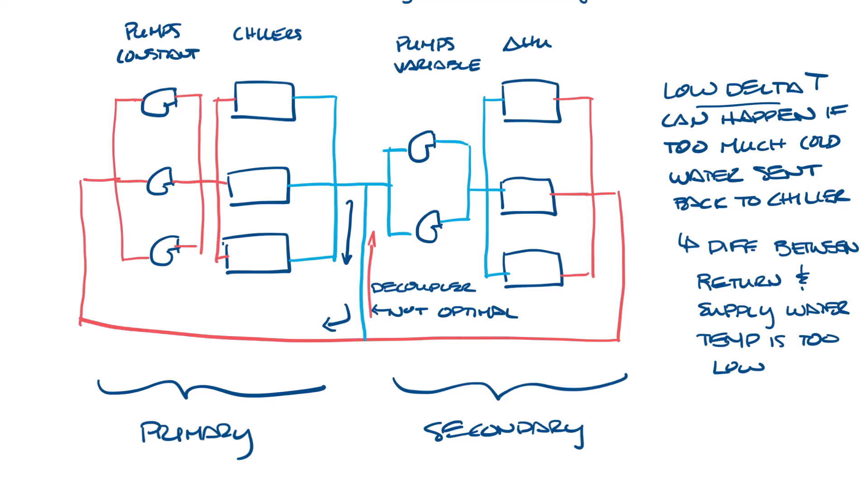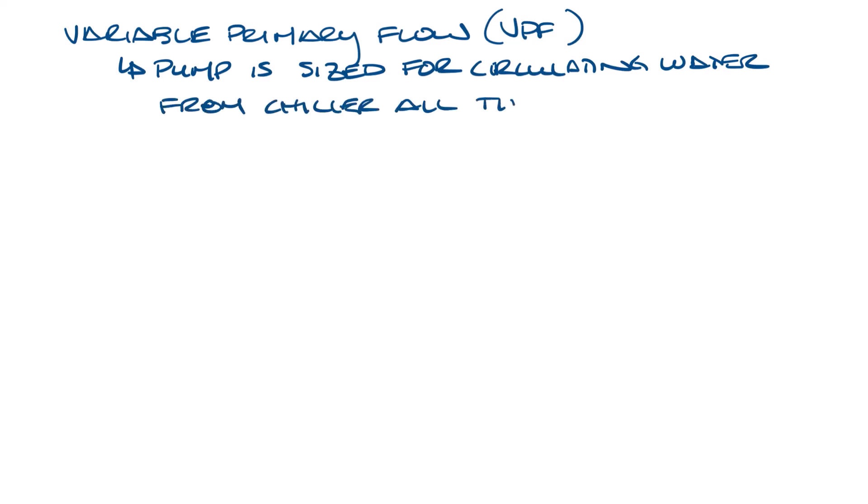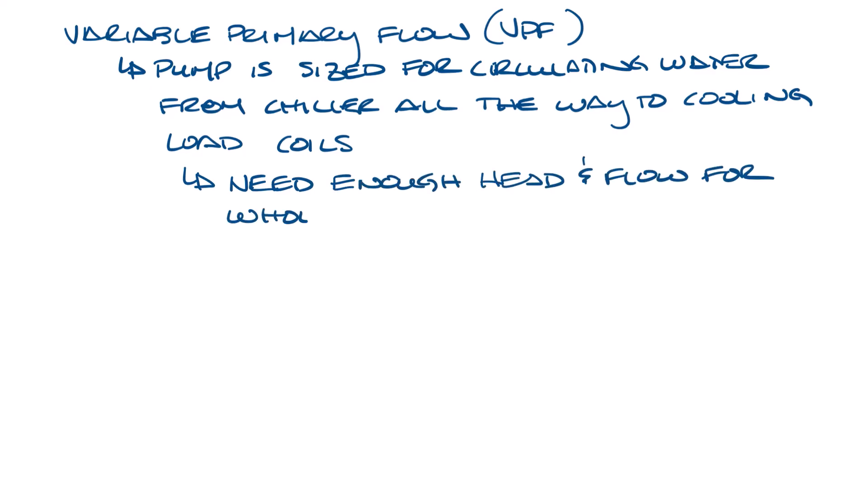So let's move this over and look at the variable primary flow circulation system. Here the primary pump is sized for circulating chilled water through the chiller and all the way to the cooling coil loads. That means that the pumps have to be sized with enough head and flow to get the water through the whole system.